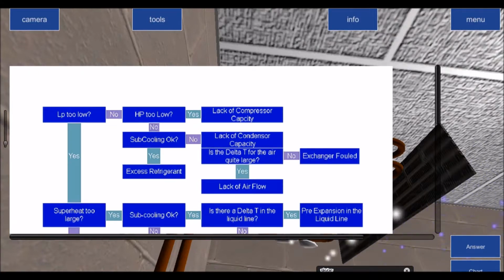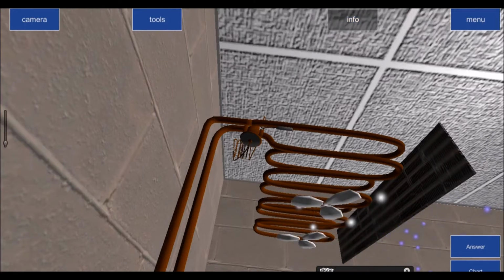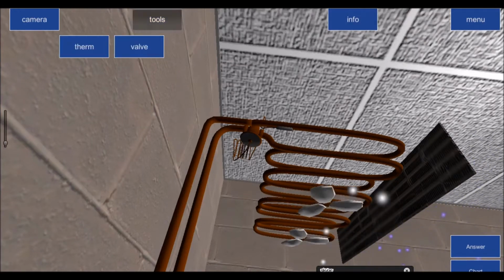LP stands for low pressure. You'll hear me talking about back pressure, and you'll hear me talking about evaporating pressure. Those three are the same. So evaporating pressure, low pressure, back pressure, they're the same. So is my evaporating pressure too low? And that's a question. But if you wanted to think of it in other terms, the question is: is it too low? Is it normal for the ambient condition that the evaporator is placed in? Or is it too high? So it all centers around the ambient condition. So again, going back to the pressure-temperature relationship, as pressure increases, temperature increases. As pressure decreases, temperature decreases.